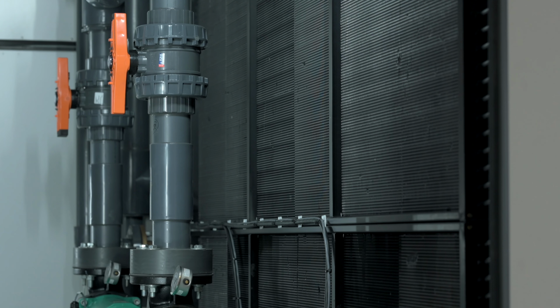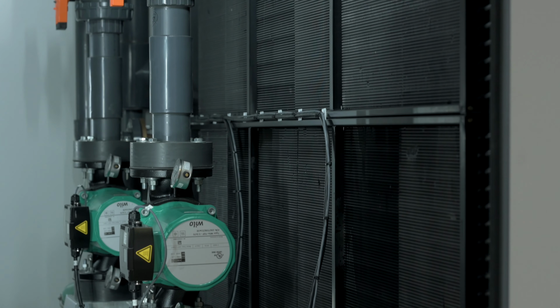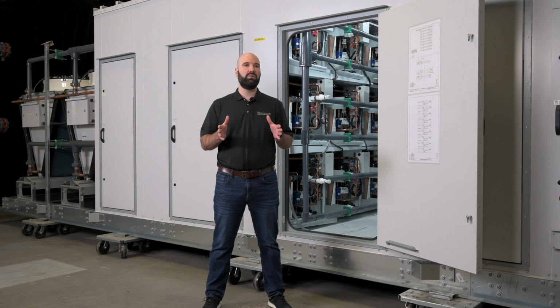And what that means for us is we've got a very repeatable process. We've got the same size refrigeration system ultimately being used in multiples across a huge range of our product line. It's very efficient to build. It's very efficient for us from a supply chain perspective, from a quality assurance perspective, but it also means that you as the customer, whether you've got an application that needs a 90-ton unit or a 24-ton unit, the fundamental technology behind it feels very familiar, and ultimately you'll have the same pods in both of those systems. It means that your maintenance guys, your mechanical contractor, they can become familiar with the technology and work on any of it.